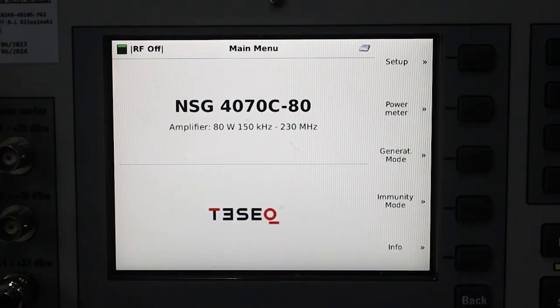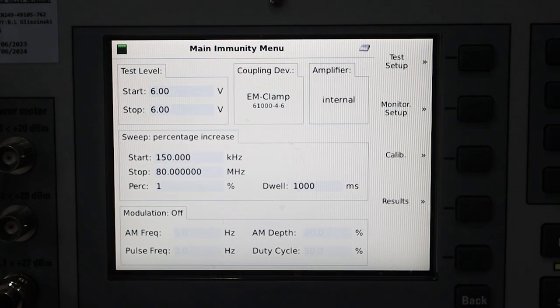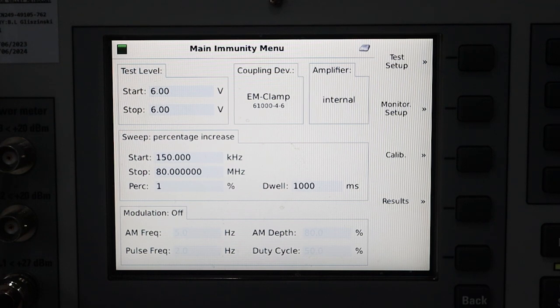All right, here we have our starting screen for our Teseq NSG 4070. Now let's get that calibration going. To do that, go ahead and go to immunity mode, and this is our general immunity mode menu.